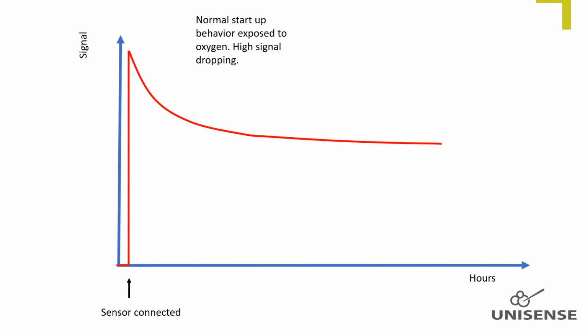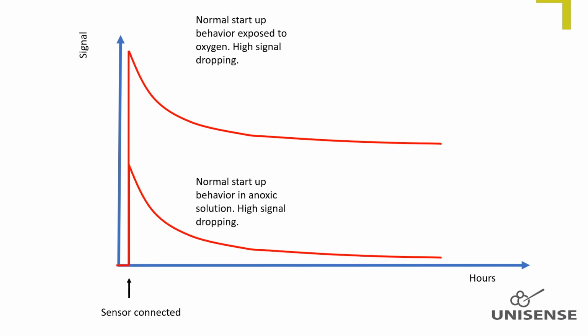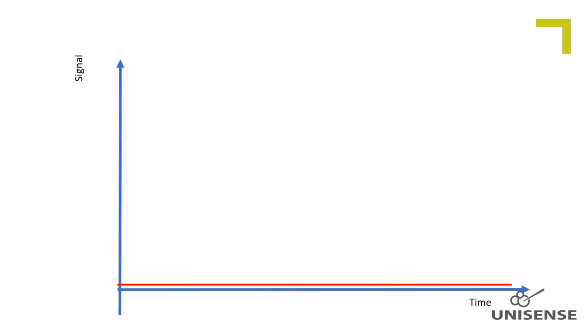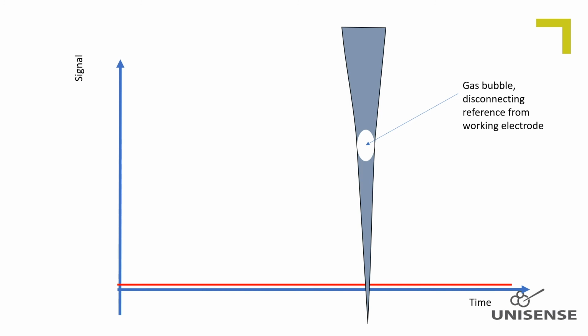These curves illustrate a normal startup behavior of an oxygen microsensor when connected to a Unisense amplifier. The signal is high and downward drifting right after connection due to reduction of electrolyte dissolved oxygen, which is slowly removed by the guard electrode. If there is not such an initial peak signal, but instead the signal does not rise much from zero, it might be due to a gas bubble stuck in the tip which disconnects the working electrode from the reference.